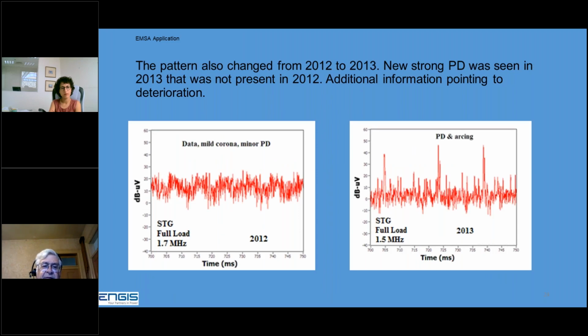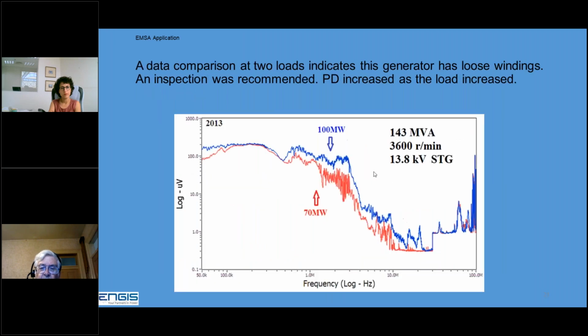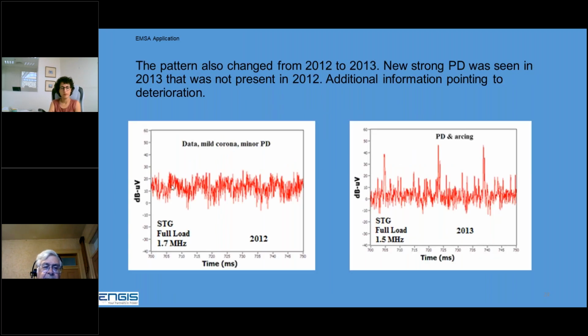The other thing that verified that was the EMI pattern that we get. This was 1.7 megahertz, 1.5 megahertz. And what we're doing is we're looking at the pattern right here. What does that EMI pattern look like? And this is what we get. It was mostly corona, looks like a sine wave, a few partial discharge spikes, really no serious problem in 2012.